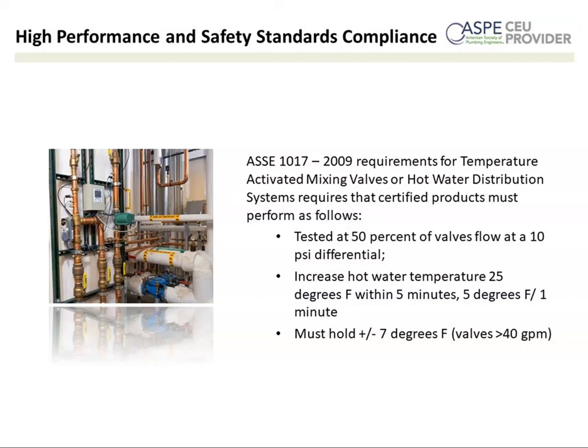And then they also have a temperature test, which essentially increases the hot water temperature roughly 25 degrees within 5 minutes. So every minute they increase the water temperature 5 degrees, and then it must hold within the set point. And the plus or minus 7, we've talked about that quite a bit. When you get into smaller capacity valves, the threshold goes down to plus or minus 5, and for really small valves, I think it's plus or minus 3 or 3.6 now. But most of the valves we sell are larger valves, and they fall into this higher capacity.